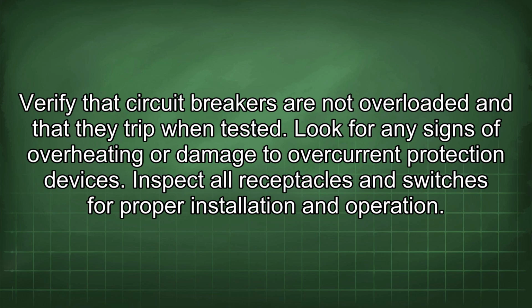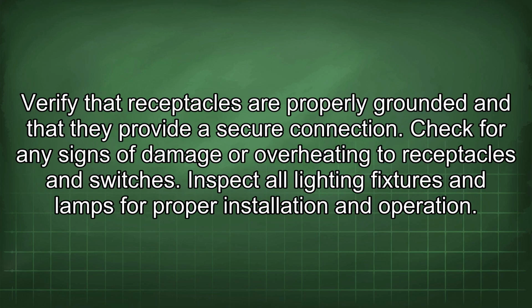Inspect all receptacles and switches for proper installation and operation. Verify that receptacles are properly grounded and that they provide a secure connection. Check for any signs of damage or overheating to receptacles and switches.